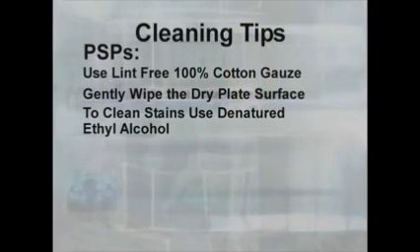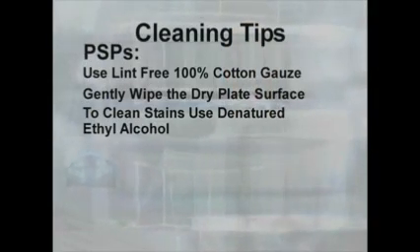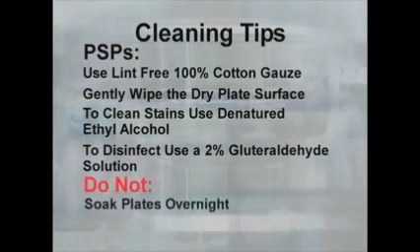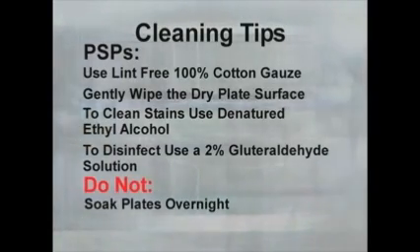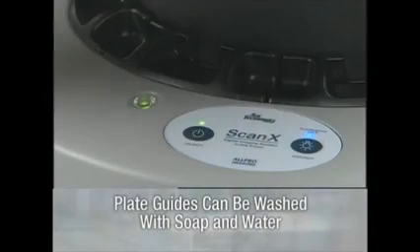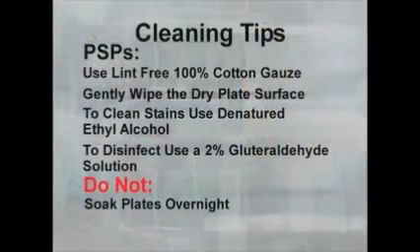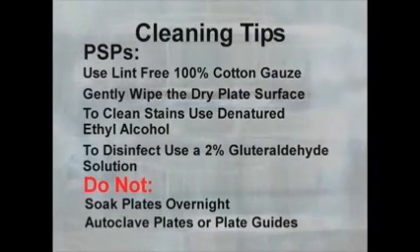A plate doesn't need to be disinfected unless you feel it's been contaminated. If a plate has come in contact with a source of contamination, a 2% glutaraldehyde solution can be used to clean it. Never soak plates overnight. After you've disinfected a plate, clean and dry it as we discussed before. The plate guides remove easily and can be washed with soap and water. Make sure you dry them completely. Never autoclave your plates or plate guides.